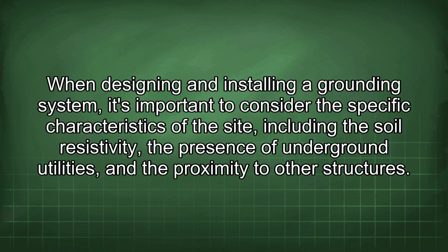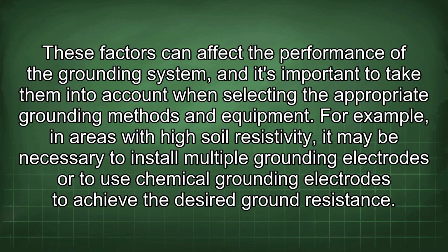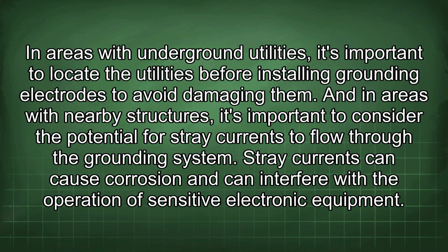When designing and installing a grounding system, it's important to consider the specific characteristics of the site, including the soil resistivity, the presence of underground utilities, and the proximity to other structures. These factors can affect the performance of the grounding system, and it's important to take them into account when selecting the appropriate grounding methods and equipment. For example, in areas with high soil resistivity, it may be necessary to install multiple grounding electrodes or to use chemical grounding electrodes to achieve the desired ground resistance. In areas with underground utilities, it's important to locate the utilities before installing grounding electrodes to avoid damaging them. And in areas with nearby structures, it's important to consider the potential for stray currents to flow through the grounding system. Stray currents can cause corrosion and can interfere with the operation of sensitive electronic equipment.